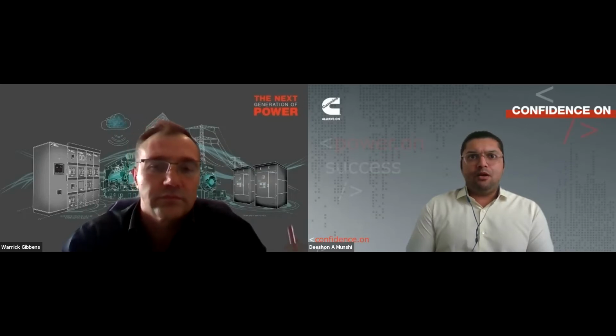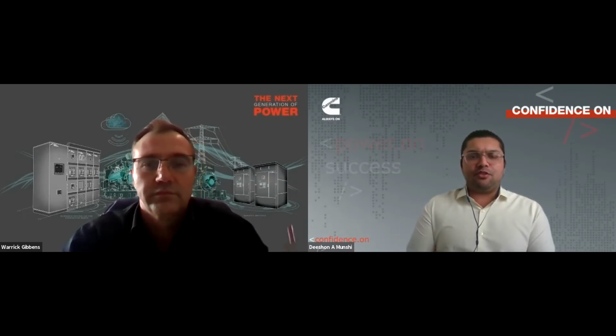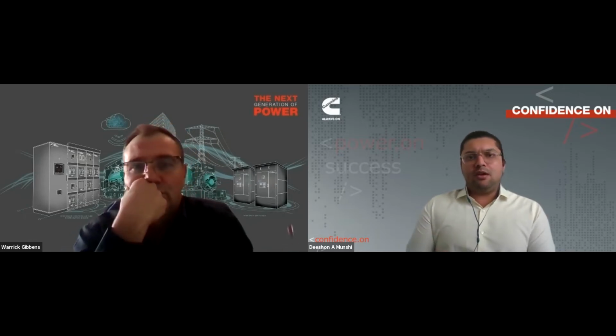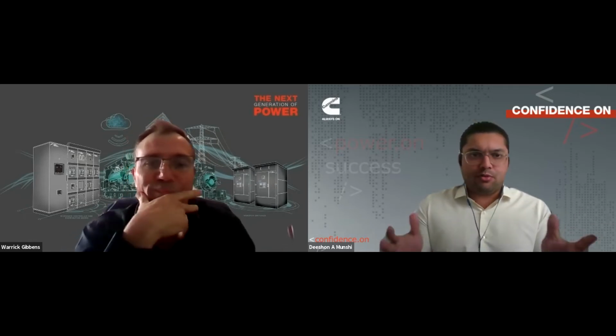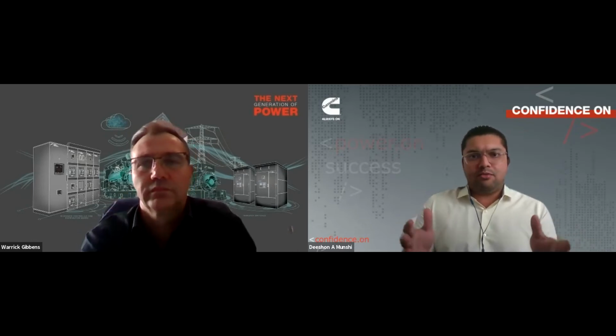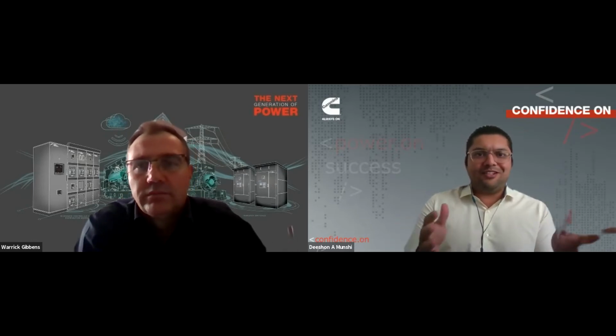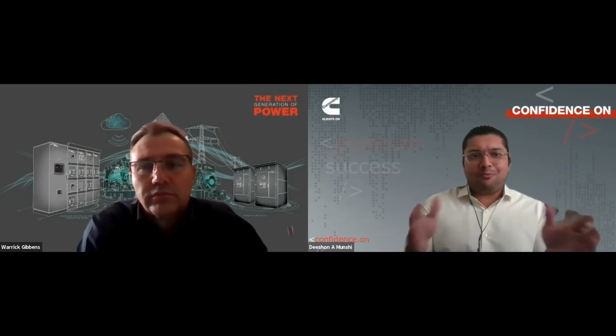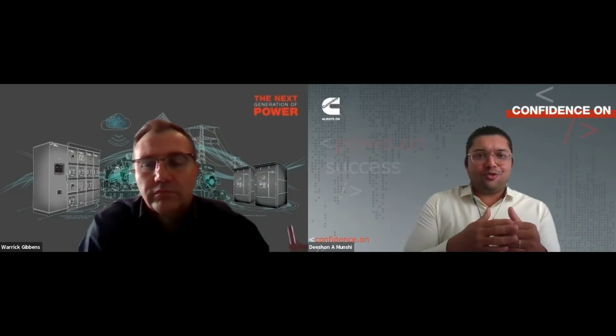Yeah, Warwick, that's actually something that I can explain quite easily. And it drives back to the question of operational costs. But before I go into operational costs, the example I'd like to give is, for example, a data center operator who comes into the Middle East knows that he's coming into an environment where his facility is going to be in a higher ambient temperature. So all the equipment, his cooling load is going to be higher, his PUE is going to be higher, right? We also know he needs to derate for that temperature.